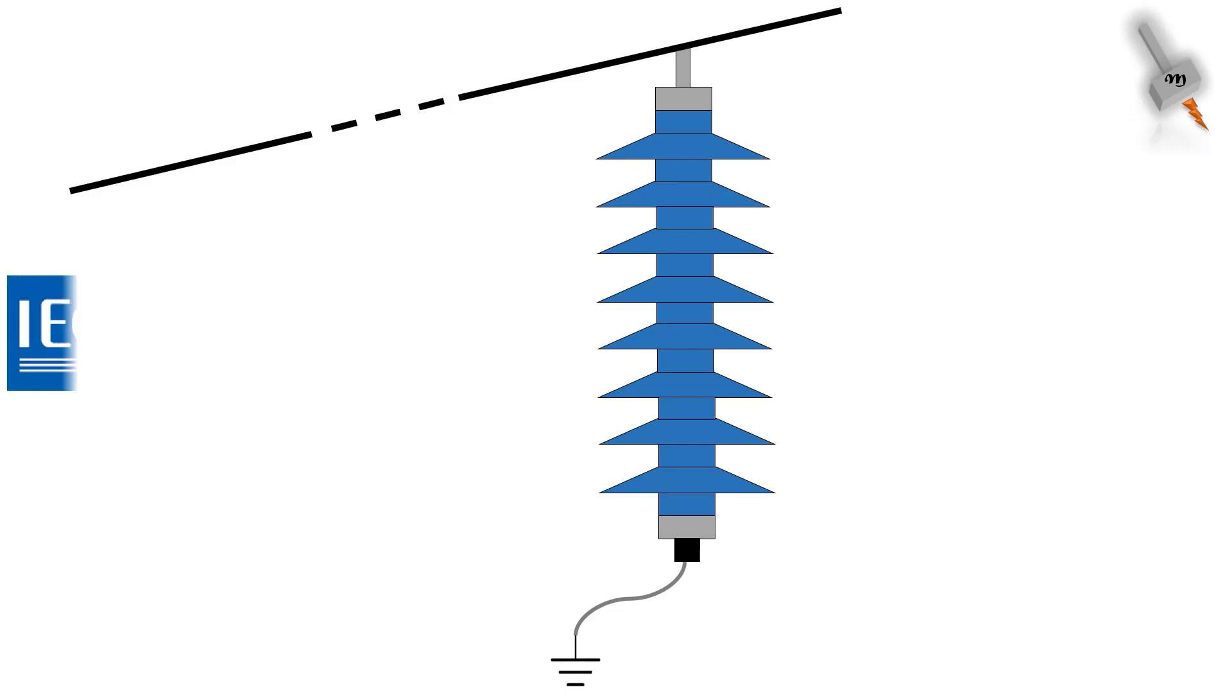Residual voltage is defined in IEC and alternatively known in IEEE standard as discharge voltage. It is the voltage across the arrester terminals when discharge current passes through it.